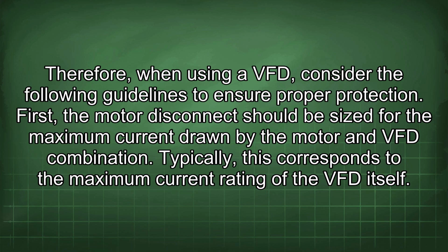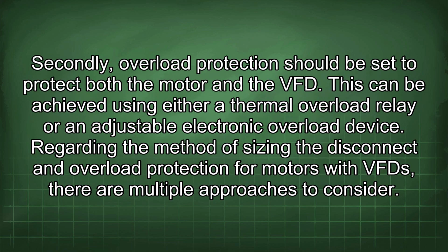First, the motor disconnect should be sized for the maximum current drawn by the motor and VFD combination. Typically, this corresponds to the maximum current rating of the VFD itself. Secondly, overload protection should be set to protect both the motor and the VFD. This can be achieved using either a thermal overload relay or an adjustable electronic overload device.